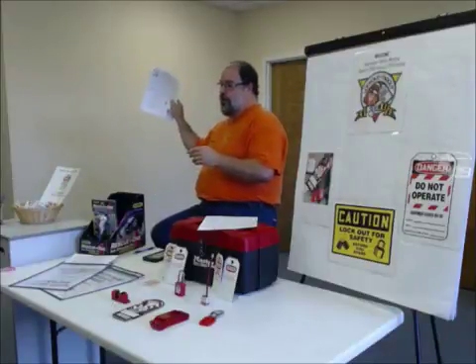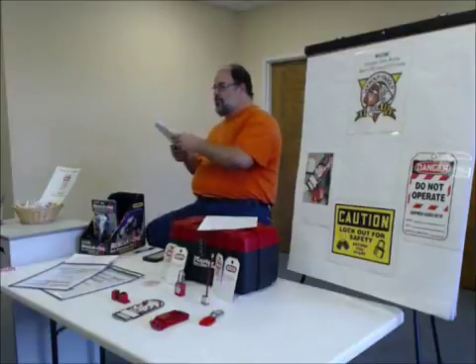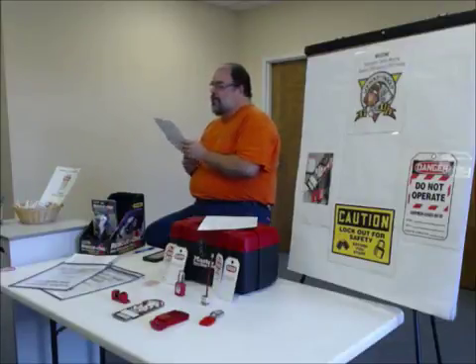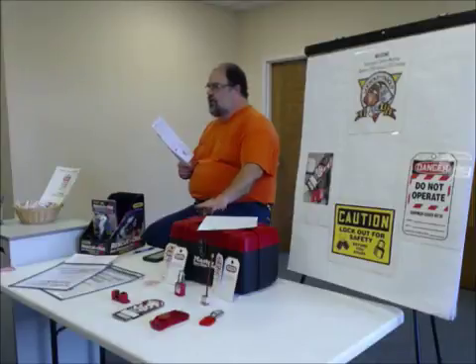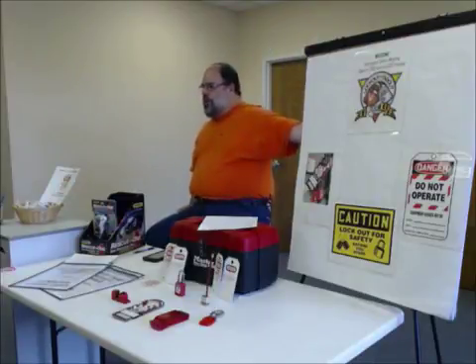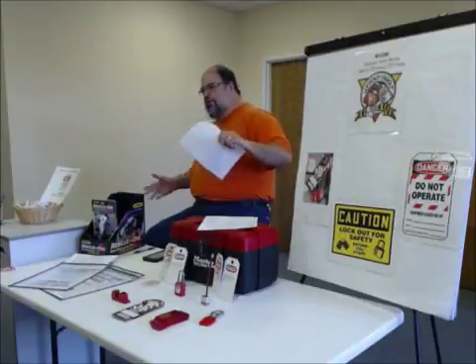Now, for authorized personnel, of whom I think there is none in here, but I still want you to be aware, I think OC, actually some paint line supervisors may be authorized to lock out equipment. But every person who's authorized to lock out should have locks of their own. That way, the keys to those locks are on your keychain, and when you're in harm's way, you have those keys with you, so you are confident that nobody can remove the lock that is protecting you because you have the only key. It's critical.